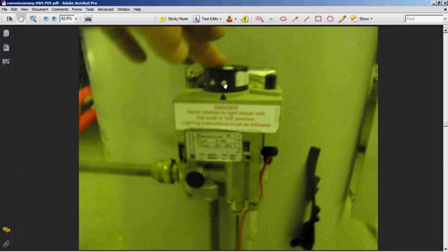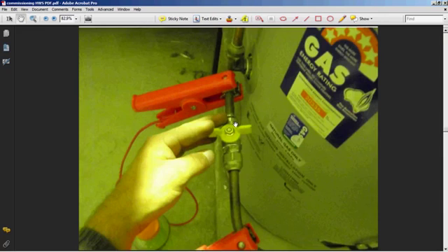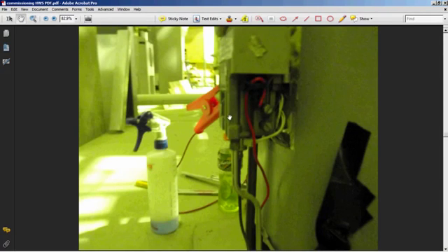Once this has been done, you can turn the appliance to the off position again and turn the gas valve off. I turn the whole appliance off again because here's your supply point screw and here is your test point screw. If you by accident take the supply pressure test point screw out and the gas valve is on, there'll be gas spewing out of this screw. So to save that accident happening in the exam, you shut the whole appliance down before you go taking test point screws out.